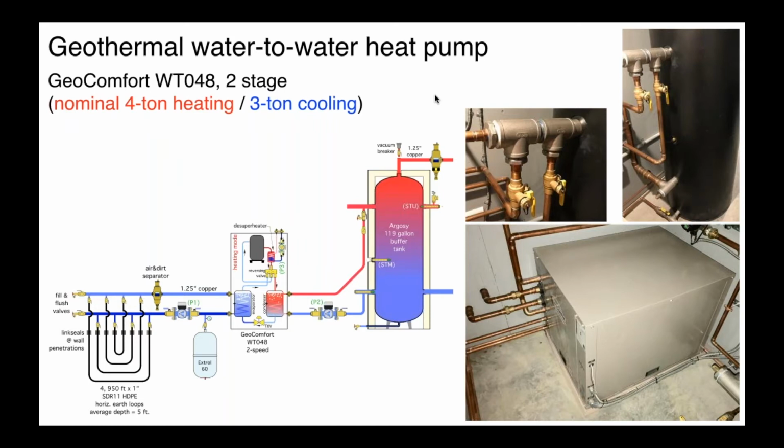next week. The garage on this house, it's a 3-stall garage. It's 24 by 32. It has floor heating in the slab, but we're not necessarily going to keep that garage heated all the time just to conserve energy. If we do turn that slab on and it is cold, some of you know that turning on a cold slab puts a very high transient load on the system. And so we wanted to have a heat pump that could address that load.